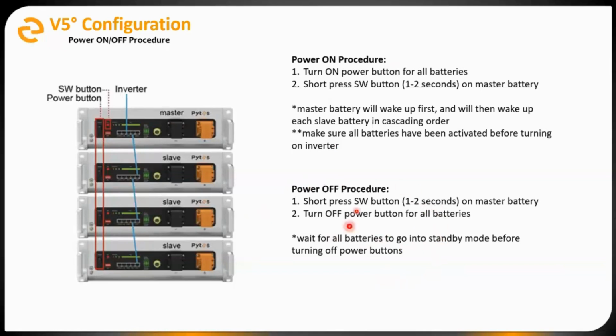And worth mentioning too, you want to turn the inverter off or disconnect the inverter before you turn the batteries off. So one really good tip I can give is anytime we're turning batteries off and on or resetting, power cycling them, we don't want the inverter trying to charge or discharge them at the same time.